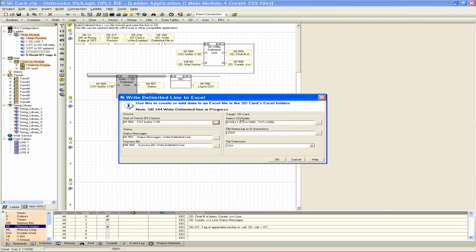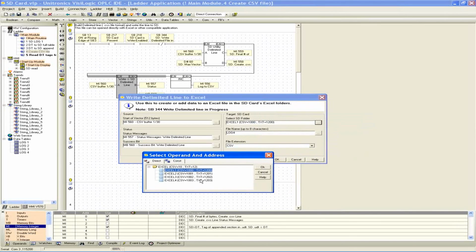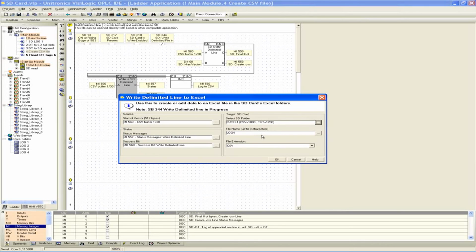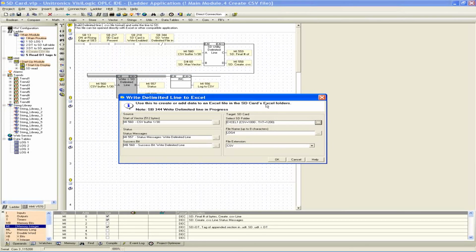That data is going to be written to the target SD card folder that we specify. Here you can see there's a special folder that was defined on the SD card for these type CSV Excel files. So here we're just writing it to Excel 1. Again, you can write it to either the root folder for Excel or any of the 4 subfolders as well. So you have to specify the target folder and then also a file name for that CSV file. Here we just called it a static value of log4. It can also be an indirect value if you wish, but here it's going to be log4 as our static file name.